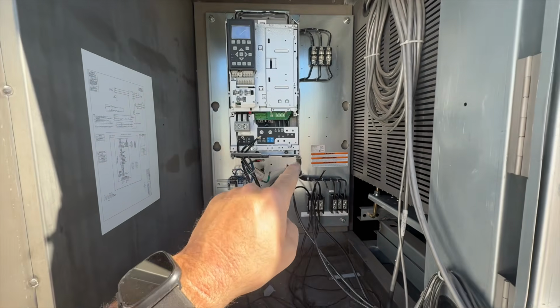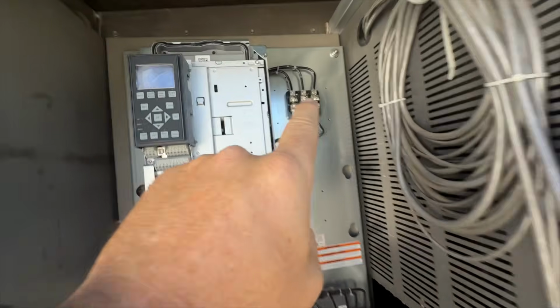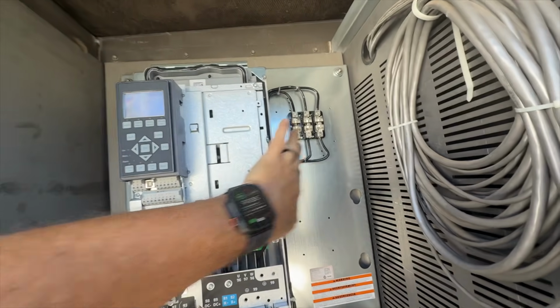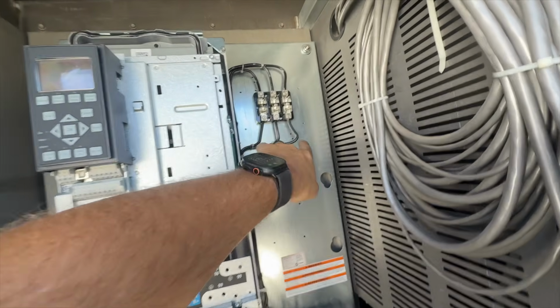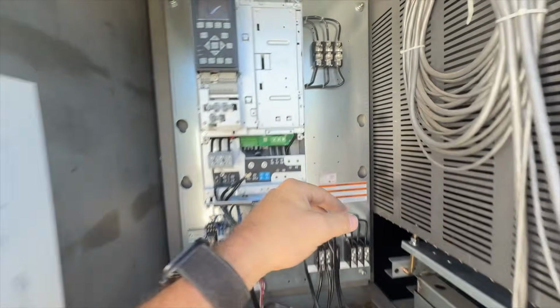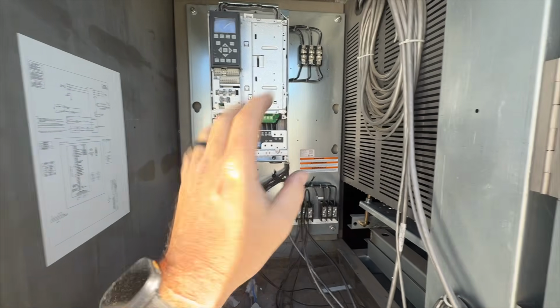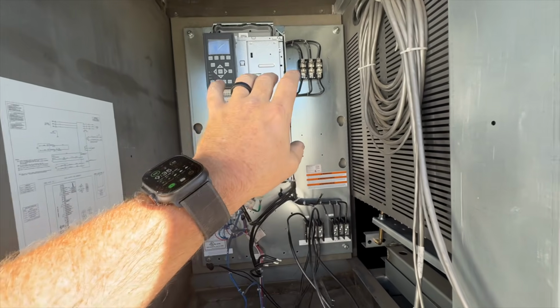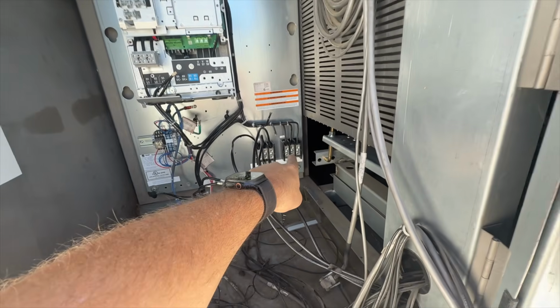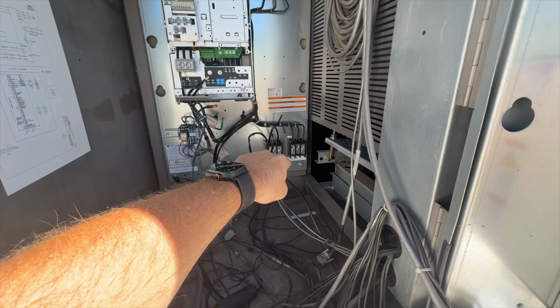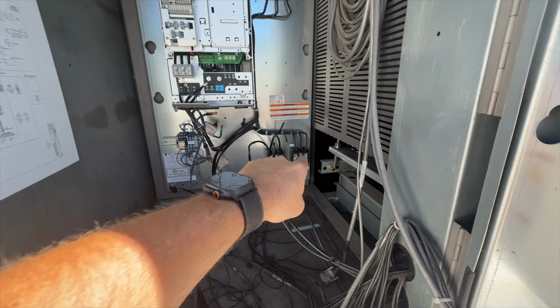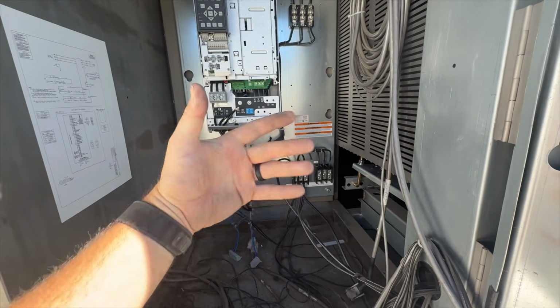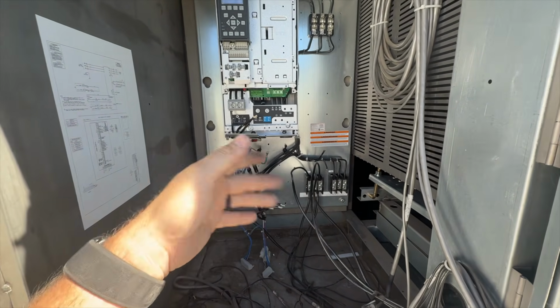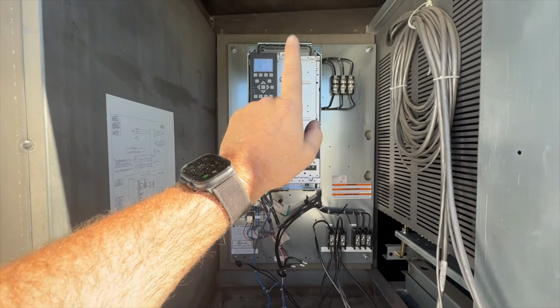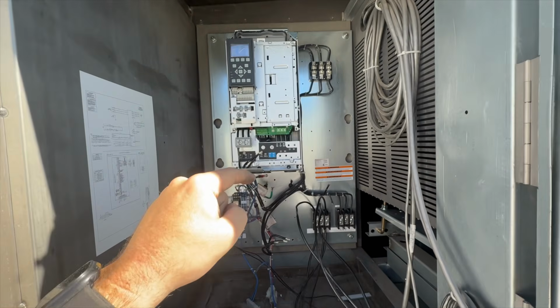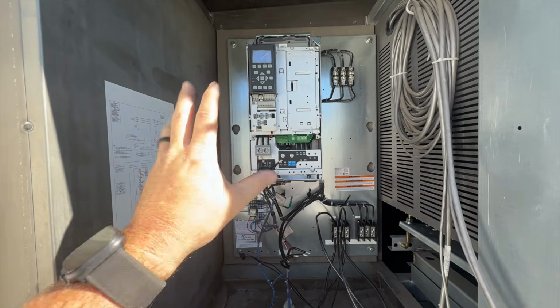But the blower motor is actually okay. What happened was, the blower motor, when it's on a VFD, never runs at 100%. So these things blew up because all of a sudden the motor's running at 100%. So the motor itself was fine. I should have hooked it up directly to the terminals because there are 150 amp fuses connected to this line input, and that's why the fuses kept blowing. I was just being dumb. But anyway, we're putting in our VFD, got new fuses in, and then we got to try to program this, and we'll see how that goes.